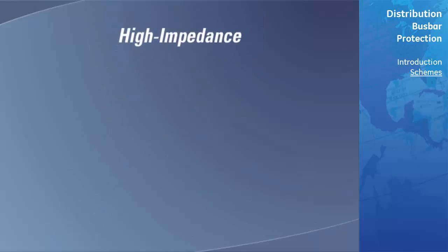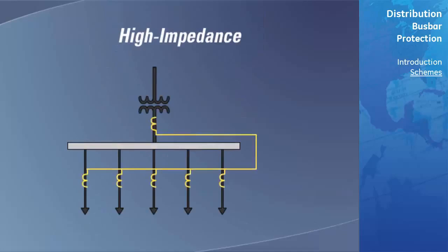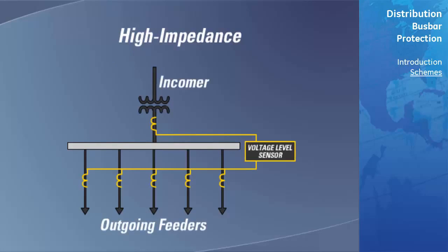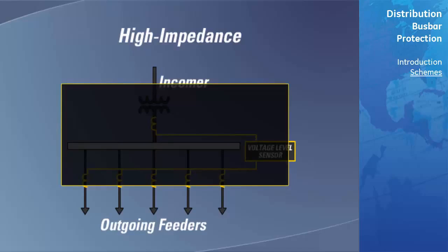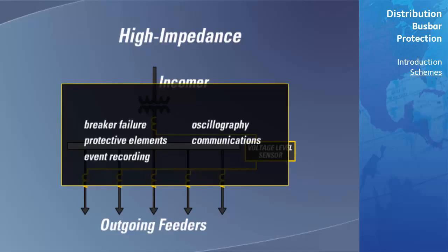The high impedance scheme requires only a simple voltage level sensor. From this perspective, the high impedance protection scheme is not a relay. If breaker failure protective elements, event recording, oscillography, communications, and other benefits of microprocessor-based relaying are of interest, then extra equipment is required, such as a digital fault recorder or dedicated breaker failure relays.